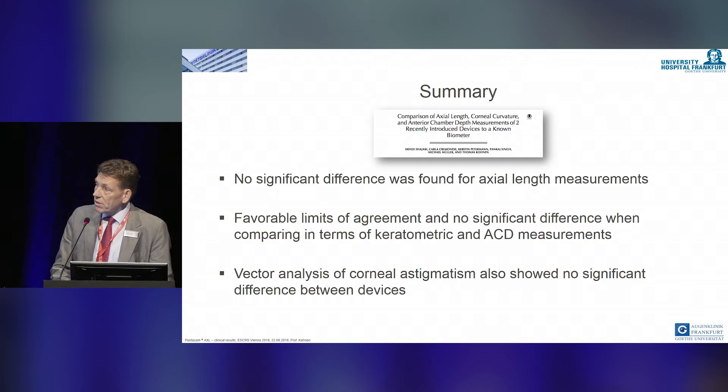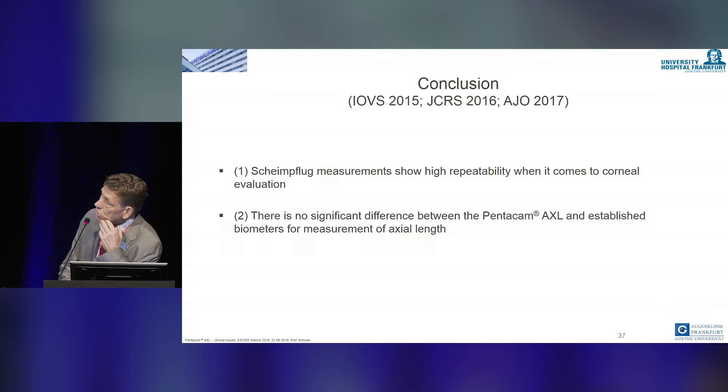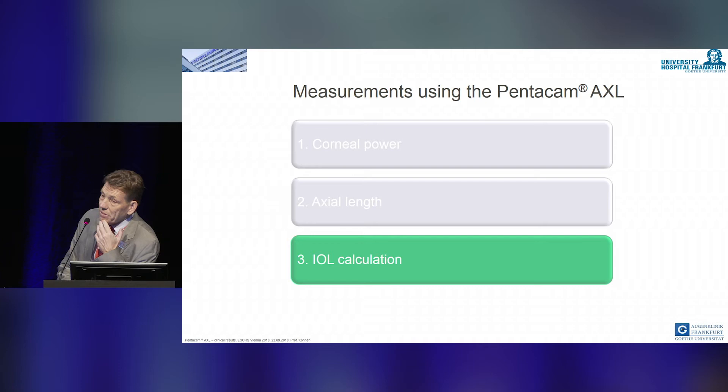So, very good information for us. In conclusion: Scheimpflug measurements show high repeatability, and we found no difference for axial length measurement compared to established biometers. Therefore, the next step is IOL calculation.